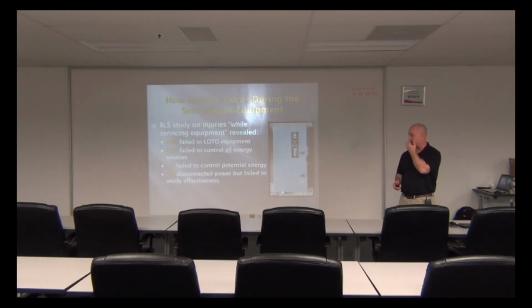Another 5% disconnect power but fail to verify effectiveness - meaning they turn off the power, and likely in this situation there may have been a capacitor within the system still holding electrical energy. They didn't think about that, so they went to work on it, but it still had electricity in it, so it shocked them. Hopefully it wasn't a big capacitor, because it could electrocute you at that point and you could die.